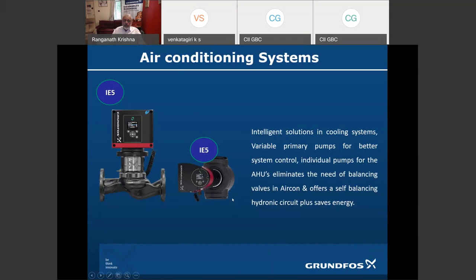which eliminates the need for balancing valves in air conditioning, offers self-balancing of the hydronic circuit, and also reduces the power consumption, because then you can size your primary circuit or secondary circuit a little lower and allow these pumps to run at variable speed to actually give you the right kind of cooling. And this can be one per AHU or one in a couple of AHUs, which then help you save a lot of power. We have seen, when we're using these pumps, easily a 30-35% reduction in the power consumption in most areas in air conditioning systems.